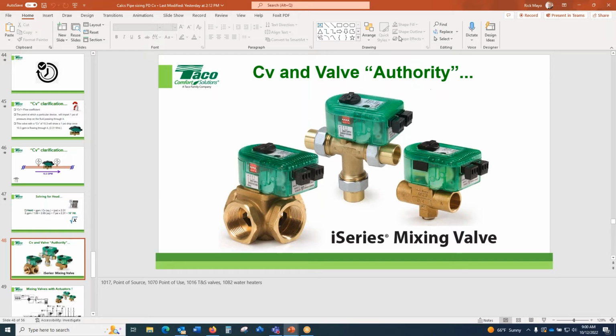So why wouldn't you make it with a larger ball? It's another thing to get molded. Here's the good thing about it. The 1 inch valve, and I'm not looking at it right now, probably has a CV of somewhere around 7 or 8. Yeah, I think it's 7.3. Okay, that's still well within the flow that you would run through the 1 inch pipe. See, 1 inch pipe is going to be somewhere, I think, 7.5 up to 10. So if I'm in there around 7 or 8 in what we're saying the CV is, that's about what I'd be running anyway. So it's not bad.